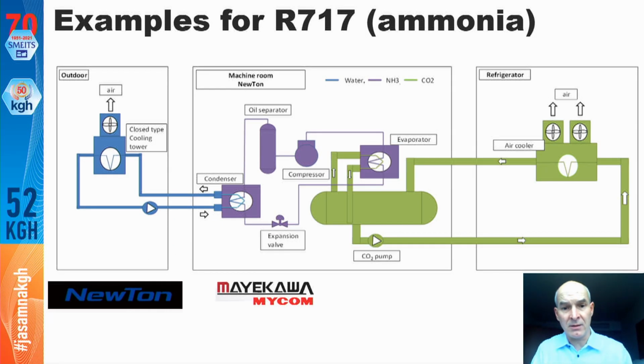This is another example of a charge reduction system. You can see that the ammonia part is in the middle of the unit, while CO2 is used to circulate through the different evaporators, absorbing heat, which is then recondensed in the evaporator of the ammonia system. By doing so, you can separate ammonia and food products and have high safety in your production plant. Even the outer unit has a kind of secondary loop, so the amount of ammonia is rather limited, and still this is a very energy efficient system.